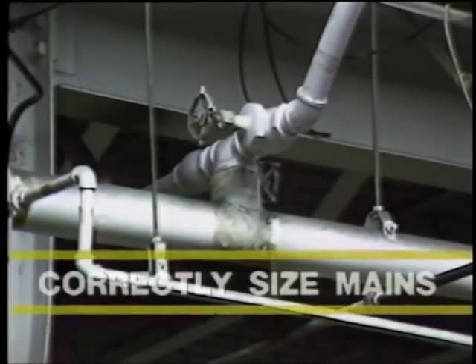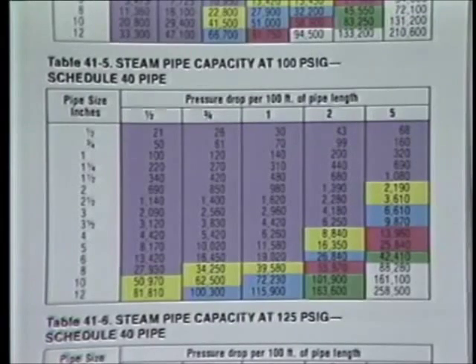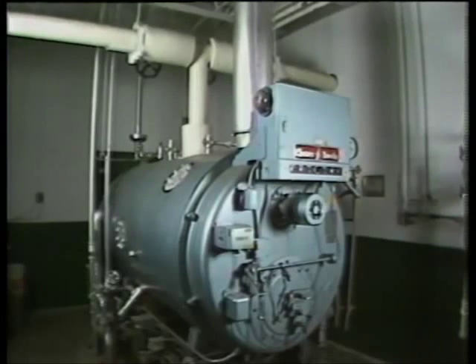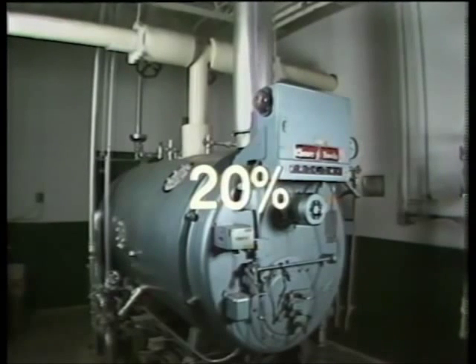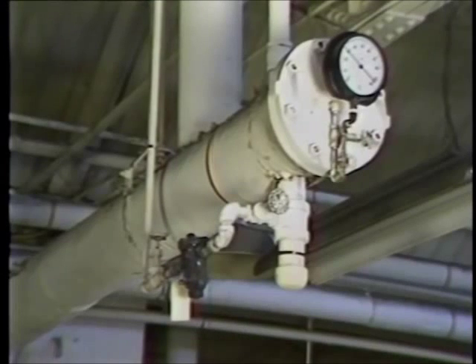Steam mains must be correctly sized to ensure efficient operation and to minimize maintenance costs. The size of the steam main piping is determined by the allowable pressure drop and velocity for a specific pressure. As velocity increases, so do noise levels, erosion potential, and the amount of pressure drop. The greatest pressure drop in the distribution system should not exceed 20% of the maximum boiler pressure, radiation and friction losses included. Remember, pressure drop is energy loss. Although the initial cost may be higher, oversizing steam mains to reduce velocities and pressure drops can help minimize future trouble and expense in your plant's operation.